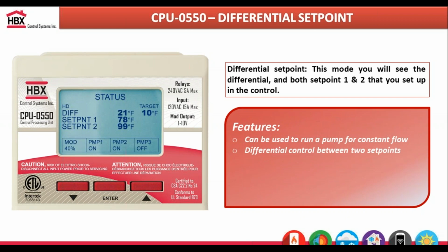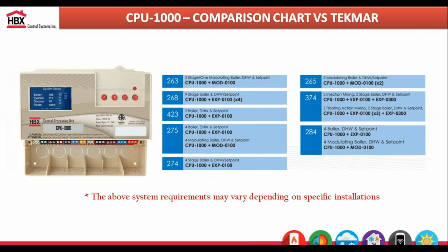You can also use this as a differential set point. So if you're transferring heat between different tanks, this is where you would probably want to use this control mode. Or if you want to use it as dual, 2 independent set points, we have a dual set point option. So just to give you the capabilities compared to a Tekmar line.